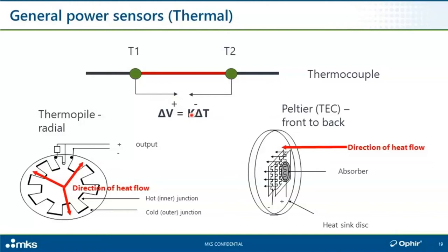There are two different configurations. Most of our sensors are based on a radial configuration where the beam is absorbed in the center, and we have a series of metal A, metal B junctions. The voltage produced is generally pretty small — a very small fraction of a microvolt or millivolt per watt of incoming power — so we have a whole bunch of these junctions. The laser beam gets absorbed on the back side; the resulting heat spreads radially outward, and the instrument measures the difference between the temperature of the inner, hotter circle and the outer, cooler circle.